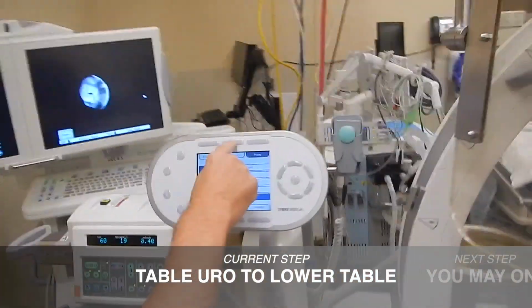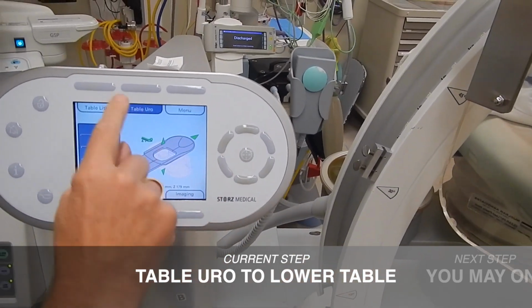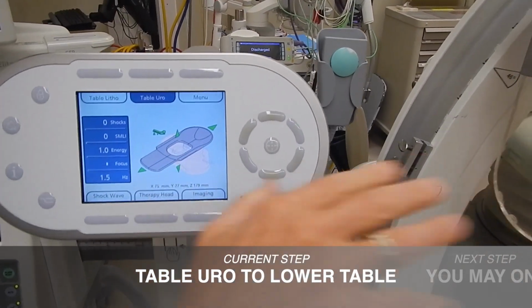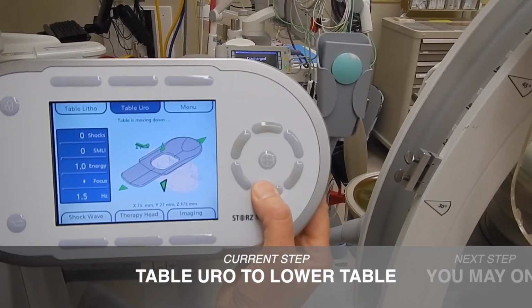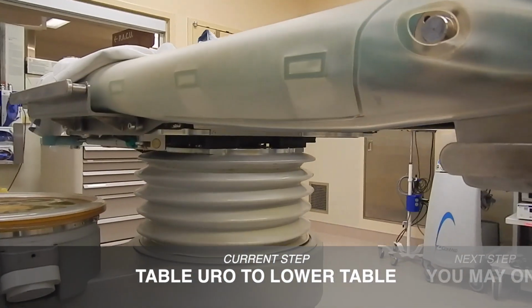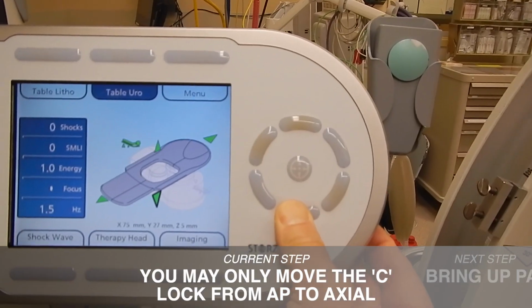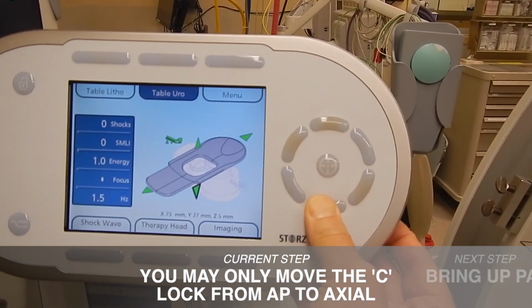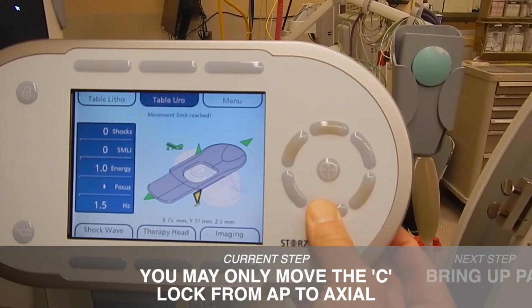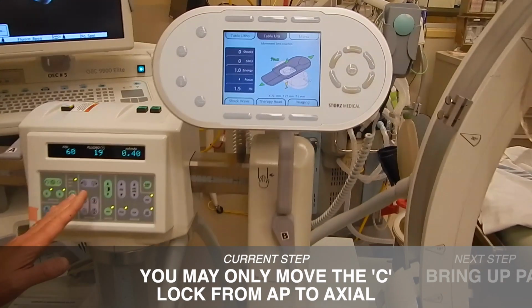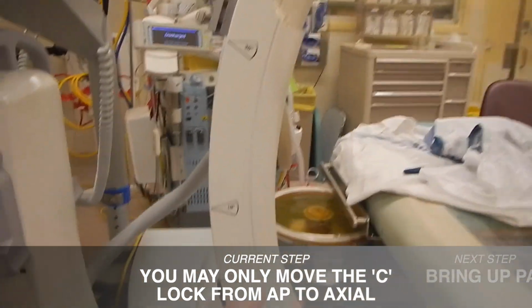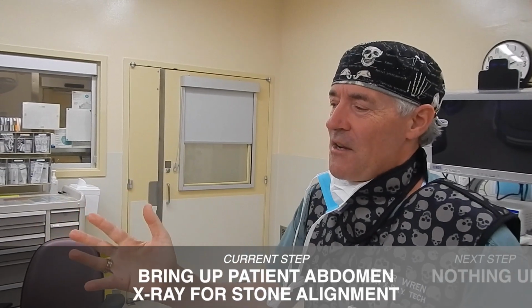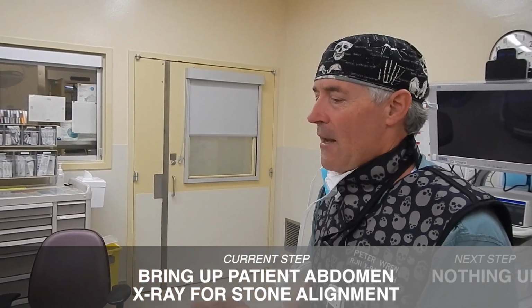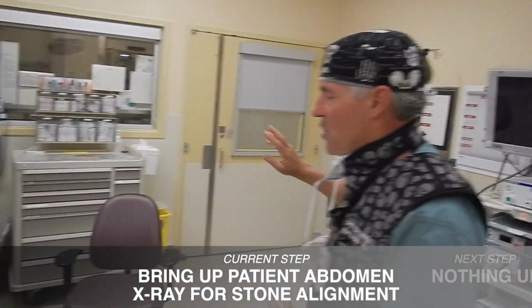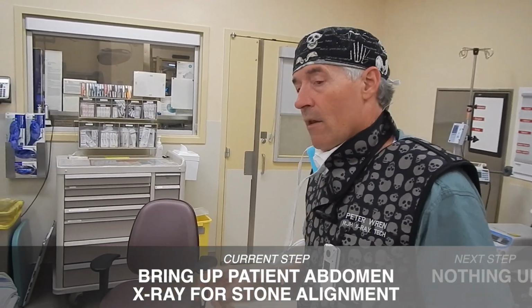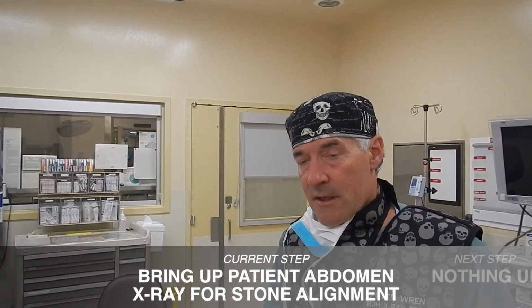Okay, so next, I'm going to prepare for the patient. The table control will bring our cradle all the way to the bottom. So it's just a matter of holding on to it. And of course, once you've got this calibrated, you don't want the C-arm to move. The only thing you move on the C-arm from here on in is the C-lock to get into your axial end. So we calibrated our C-arm to the therapy head, and now we have a patient on the table. The patient will come in on a stretcher, and they would have had an x-ray prior to this.